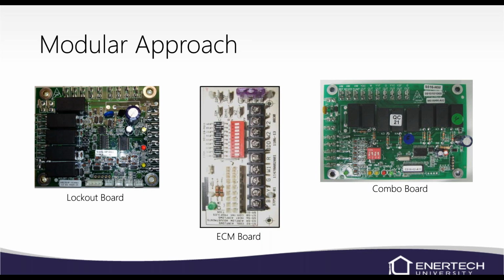We've got a lockout board that looks almost identical to this one here in the picture, except some of the jumpers are different. And on the newer board, on the very bottom, you can see there's some 4 little white boxes where we're looking at some thermistors and things. And we'll cover those as we go along, but the older board did not have those. But this newer board, if you were just to keep it on your truck, we could put it on an older unit and get it to work. So it's backwards compatible.